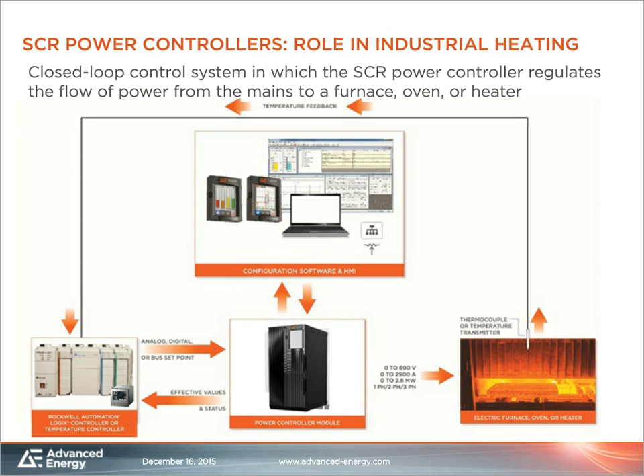That set point is generated either by a PLC, for example the Rockwell Automation Logix controller, or a temperature controller. The set point signal refers either to power, to voltage, or to current, and the power controller regulates the electrical power flow to the heating elements according to this set point. The set point is generated according to a temperature feedback signal, created either by a thermocouple or by a temperature transmitter from the electrical furnace. That's the input — the whole thing is the outer control loop.